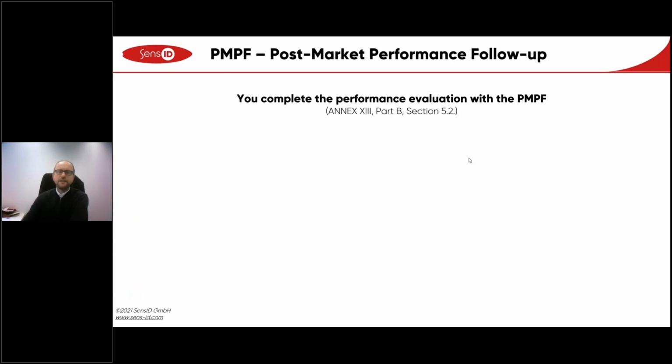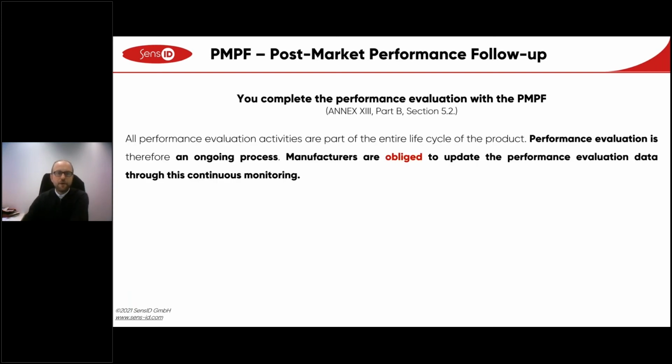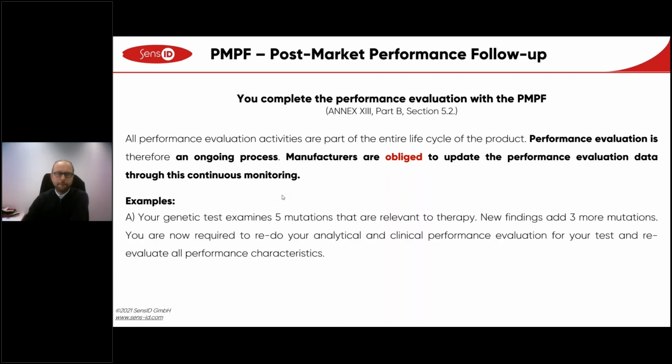So you complete the performance evaluation with the post-market performance follow-up. And as all performance evaluation activities are part of the entire life cycle of the product, you have to do the evaluation activities again and again and again. Performance evaluation is therefore an ongoing process, and manufacturers are obliged to update the performance evaluation data through this continuous monitoring. Here we have two examples.